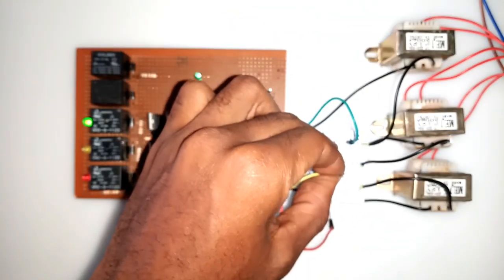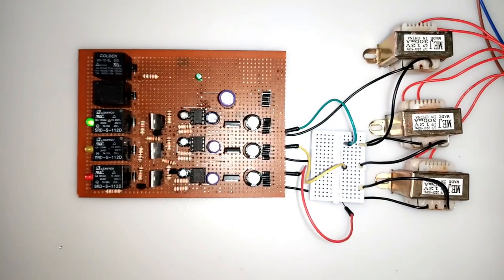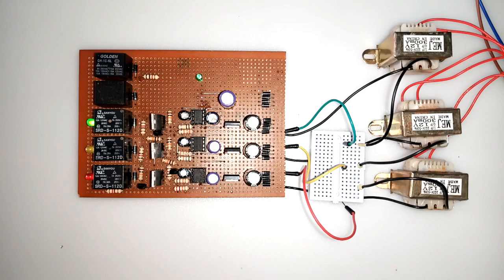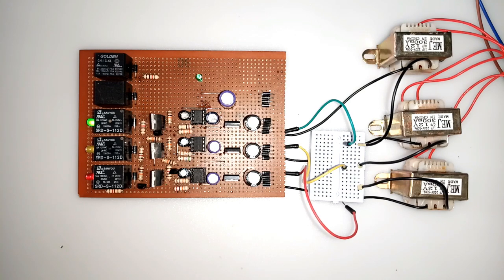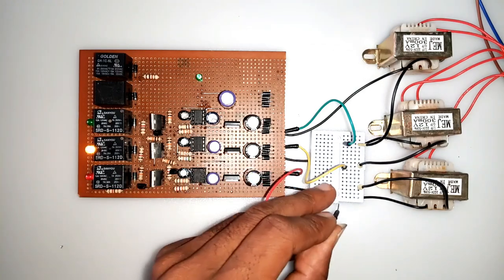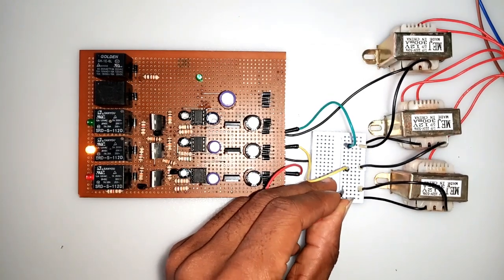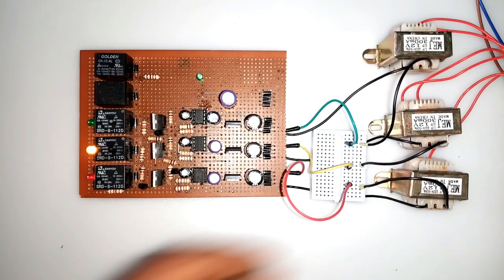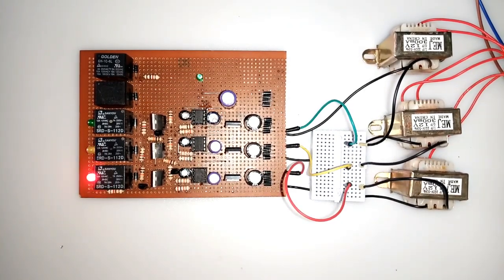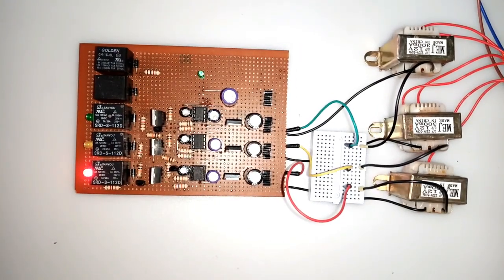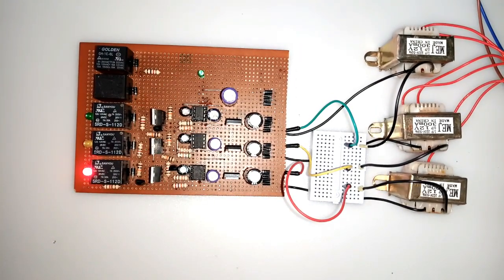And that tells you all you need to know. So once the yellow phase is now plugged in, it will take 10 seconds and then switch back to the yellow phase. Now once the red phase is back on, it will take 5 seconds and switch to the red phase. And that tells you all you need to know and that is the system working perfectly as per design.